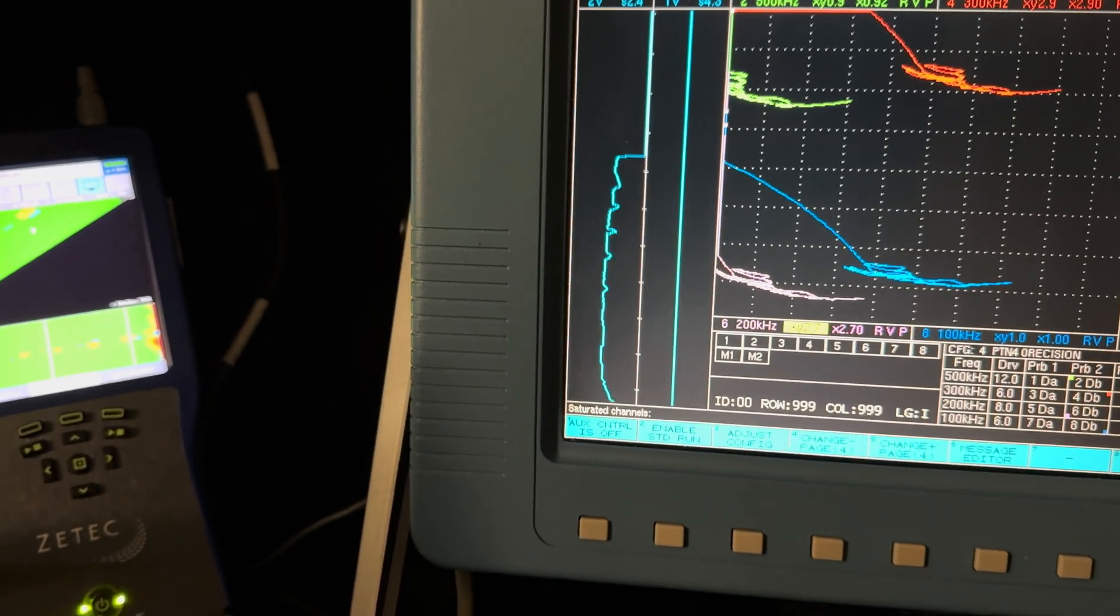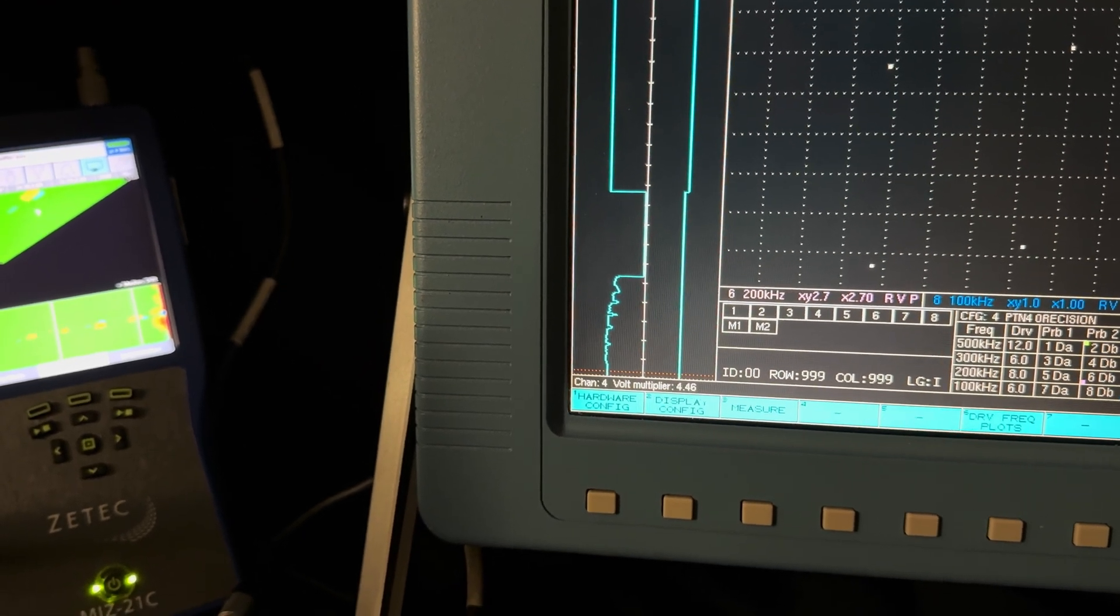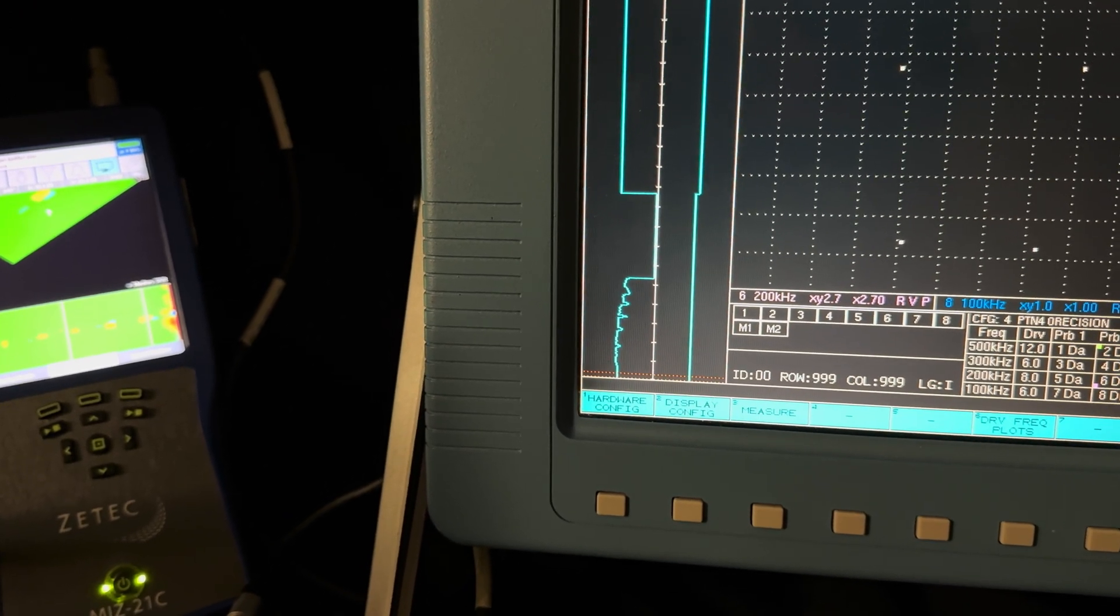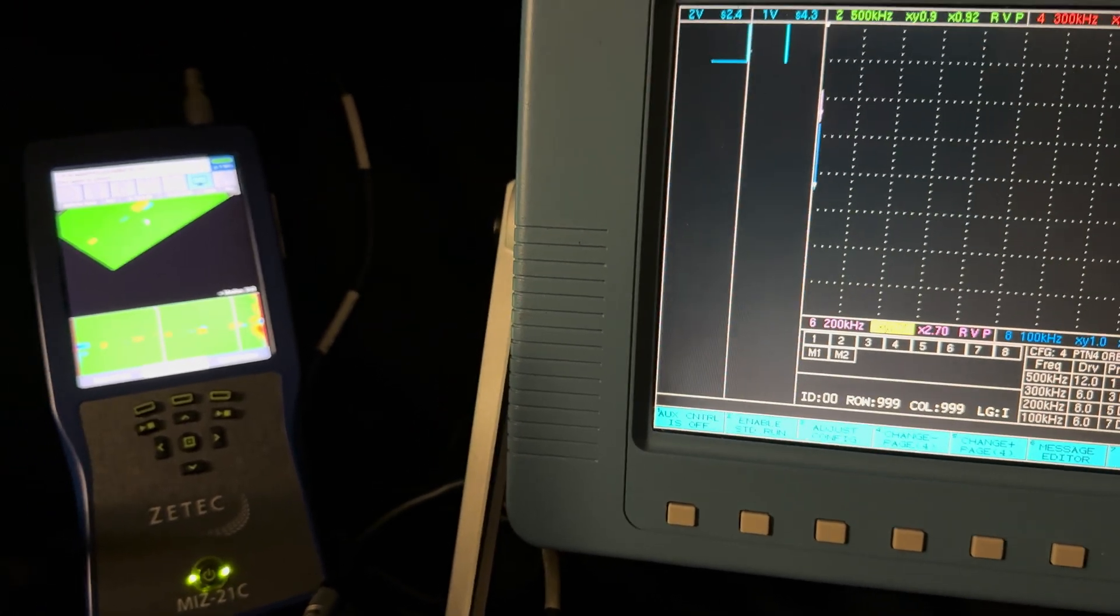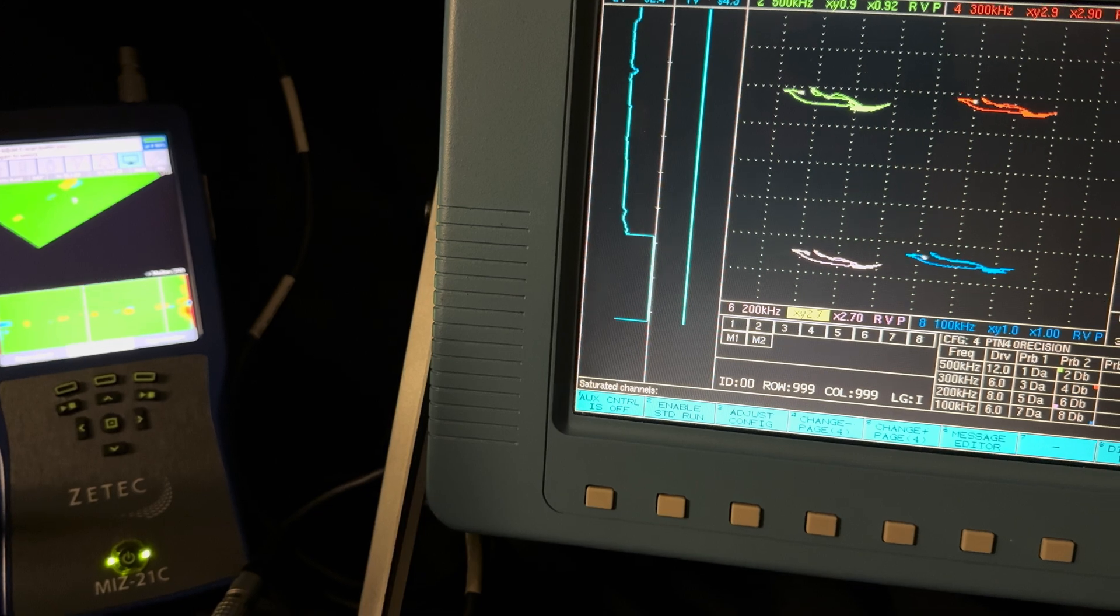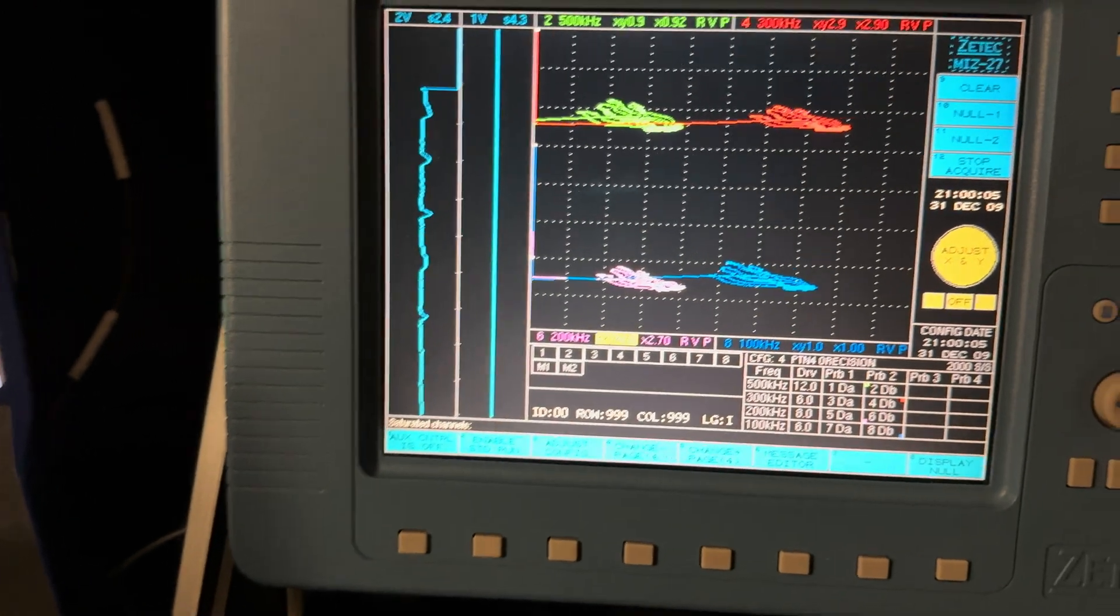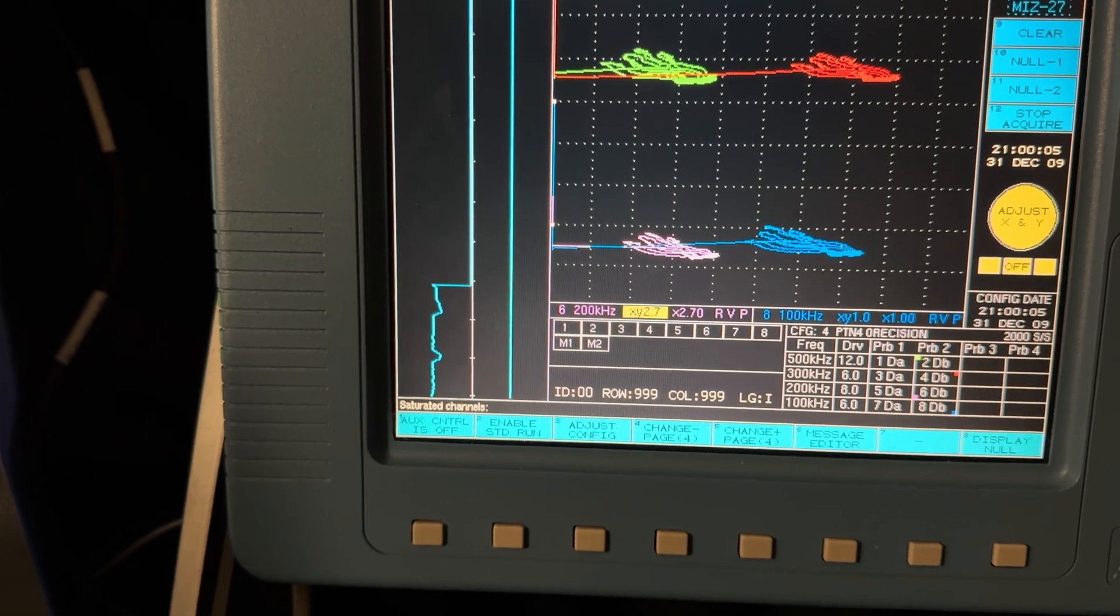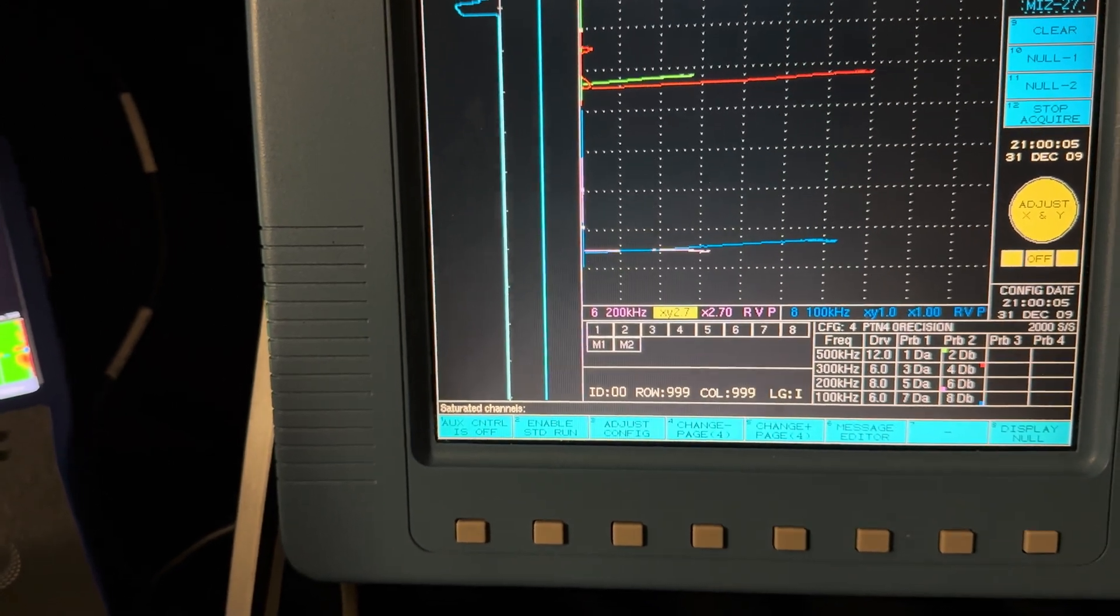Okay, let's try this another way. You can hang in there for the video. I've been here since six o'clock this morning making this video, so just hang in there, be patient. You're gonna see all sorts of great stuff. So I just moved the null point a little bit so hopefully they'll stay on screen a little better. One, two, three, four, five. All right, so this is multi-frequency testing. The green data is 500 kilohertz, the red data is 300 kilohertz. The blue data is 100 kilohertz, purple data is 200 kilohertz.